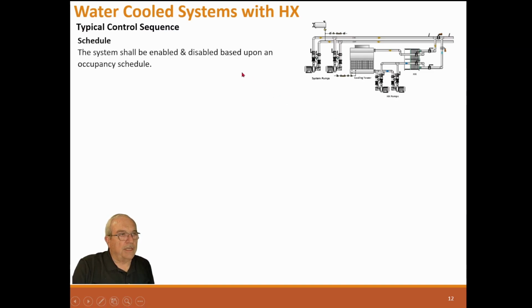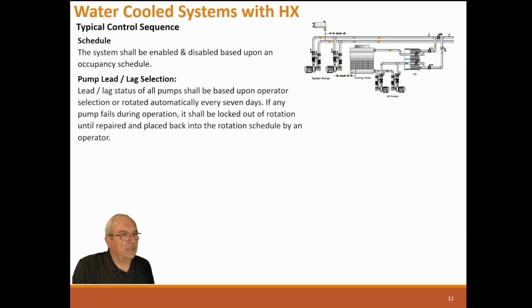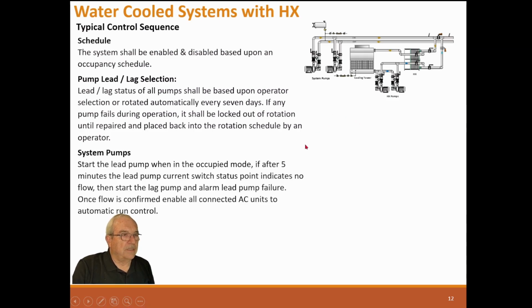Let's look at the sequences. Again, we have a schedule. Systems to be enabled and disabled based upon an occupancy schedule. Pump lead-lag, same thing. We're going to lead-lag the pumps. If one fails, we're going to start the lag pump and alarm that we have a pump failure, and those are going to be locked out until they're fixed and put back in operation by an operator. System pumps start the lead pump when it's in occupied mode. If after 5 minutes the pump current switch status point indicates no flow, then start the lag pump and alarm the lead pump failure. Once flow is confirmed, enable the AC units. That applies to these pumps, and it applies to these pumps, but they'd be on a VFD. So instead of a current switch, it'd be a VFD telling you that it's not running.